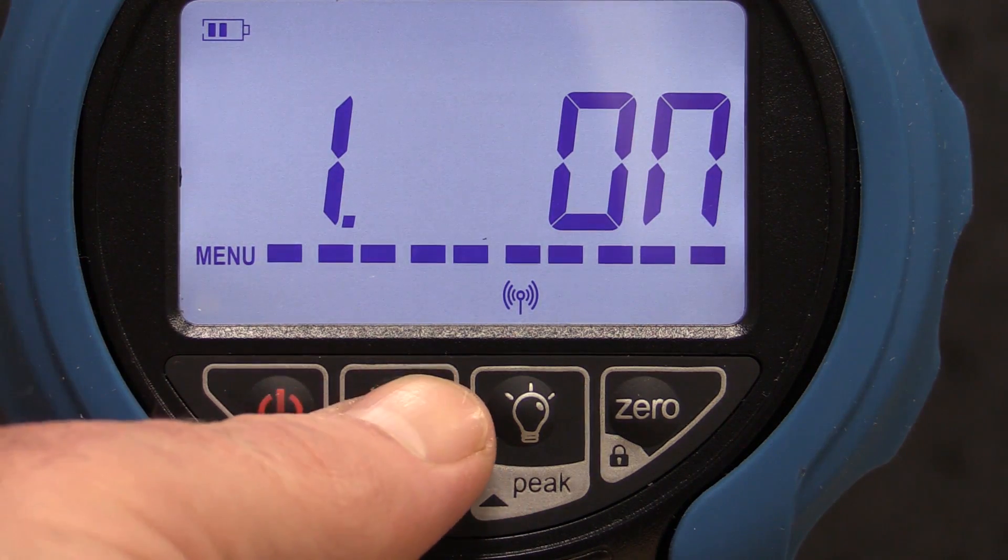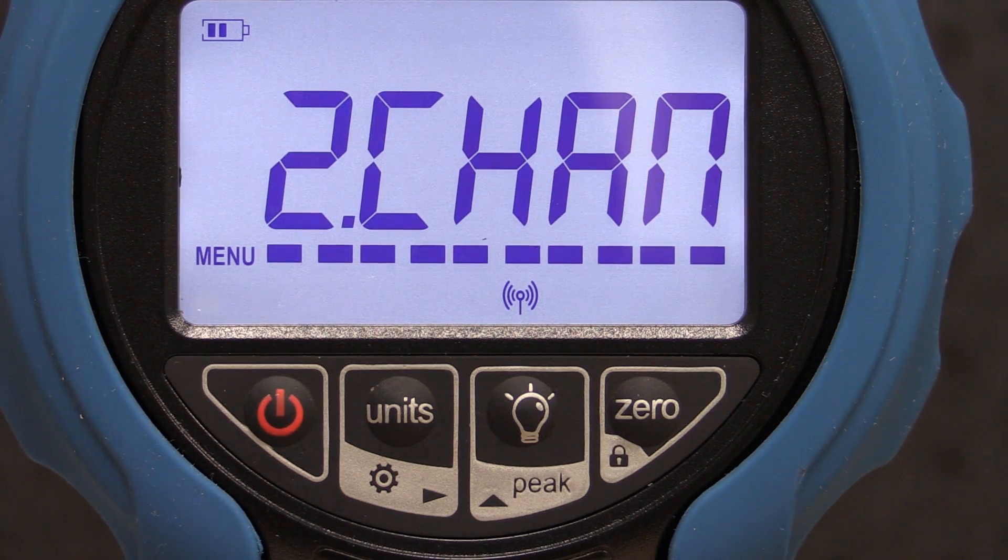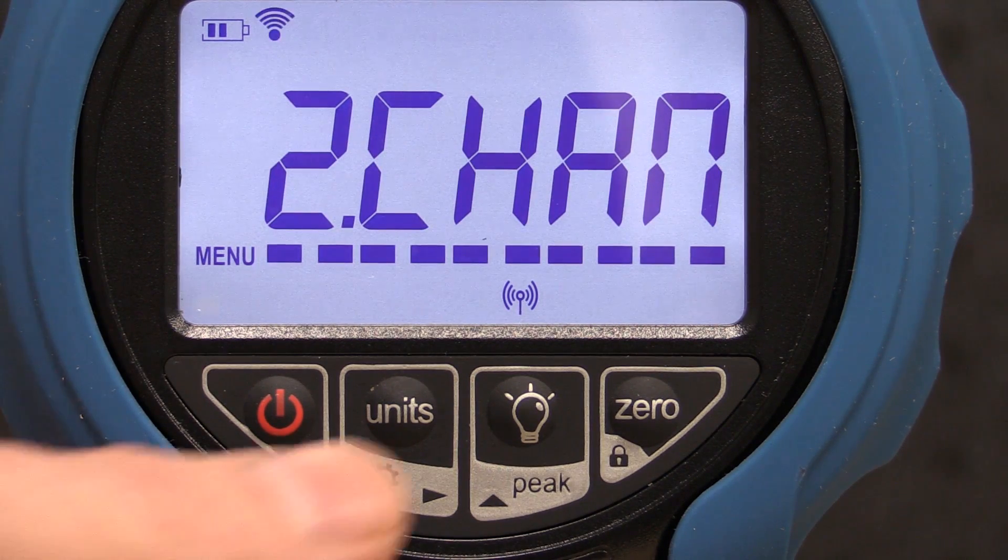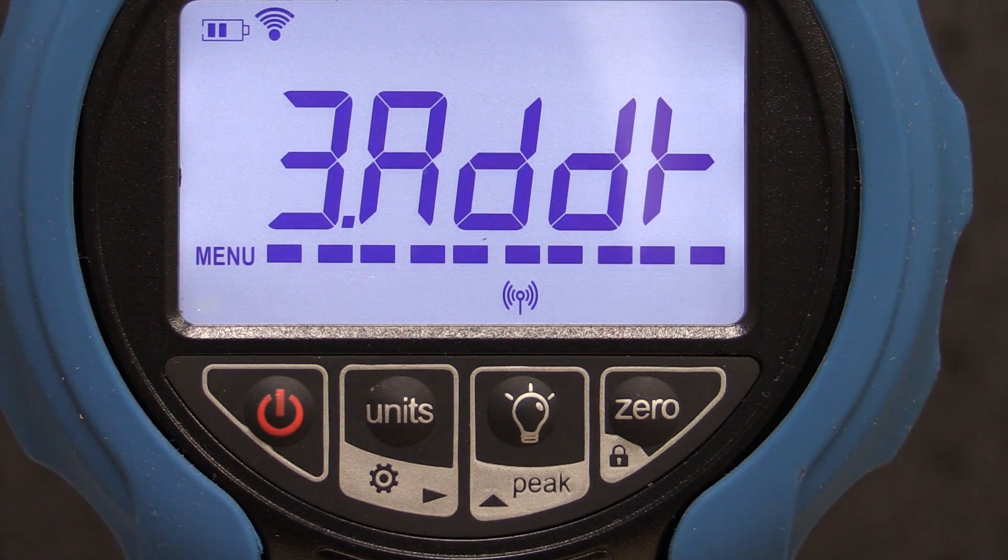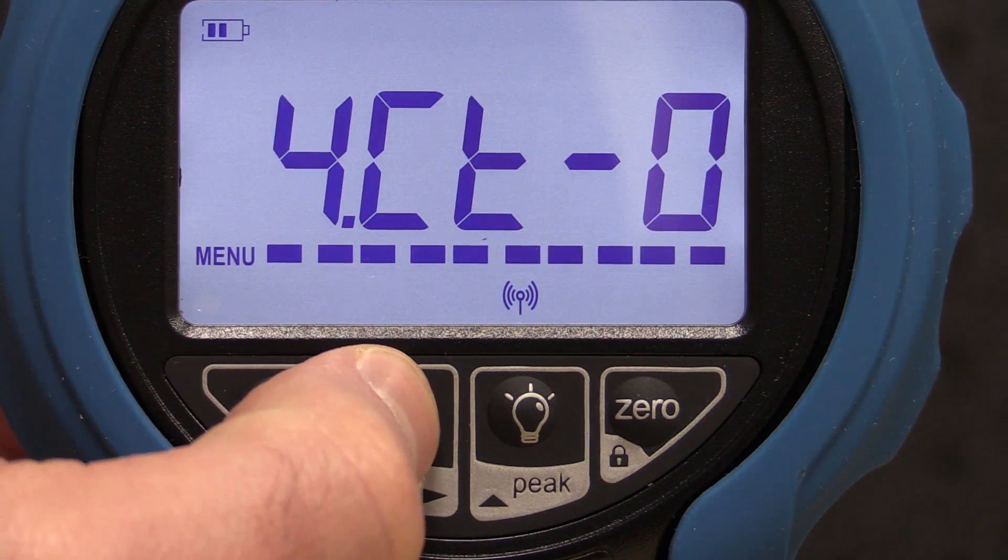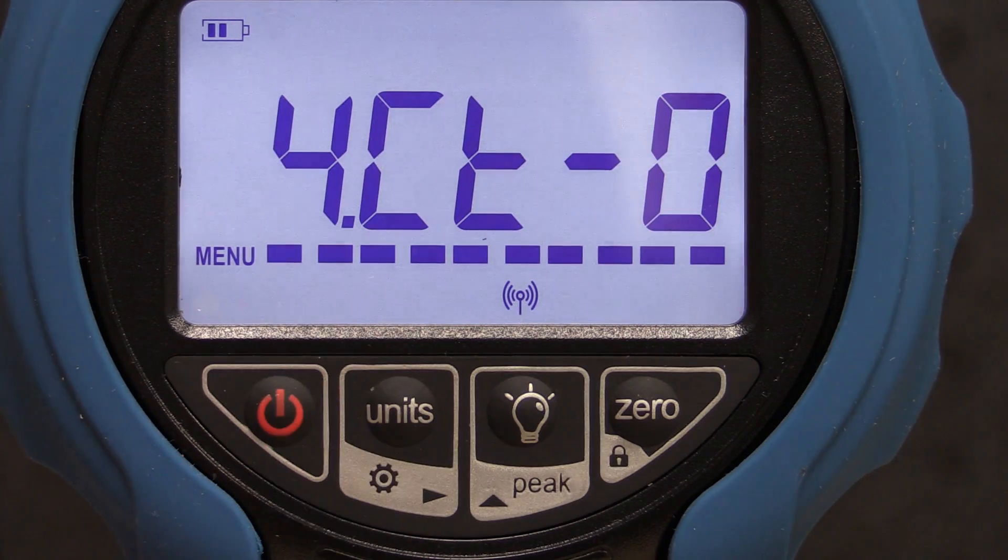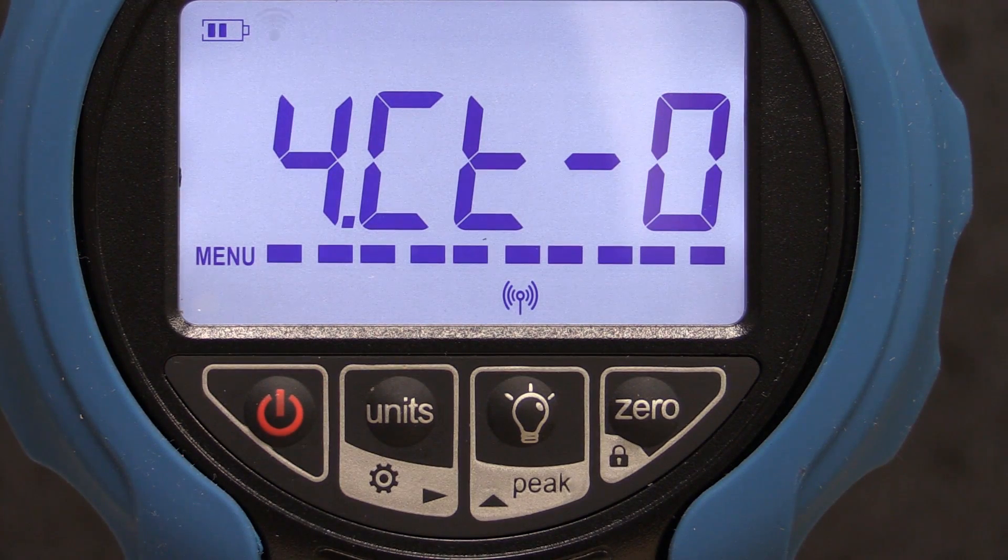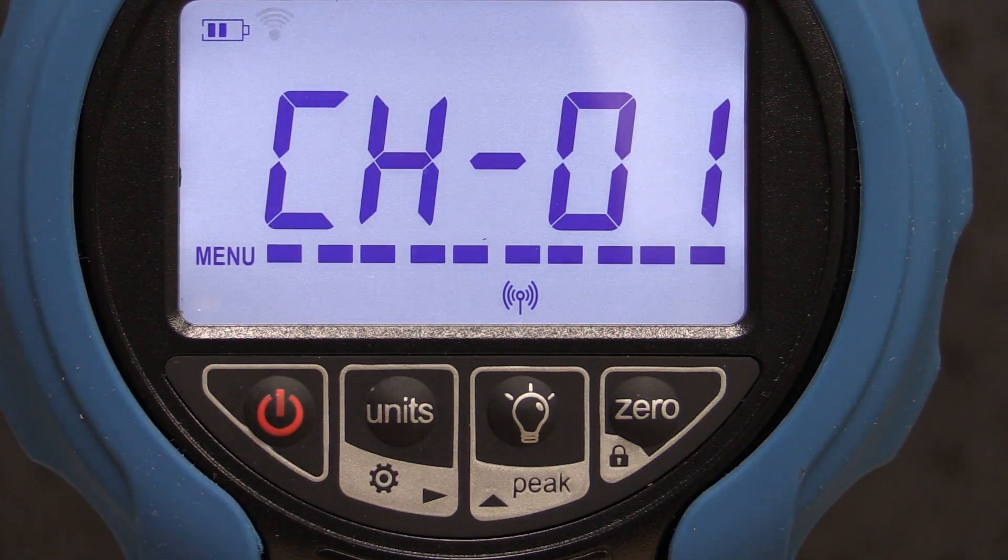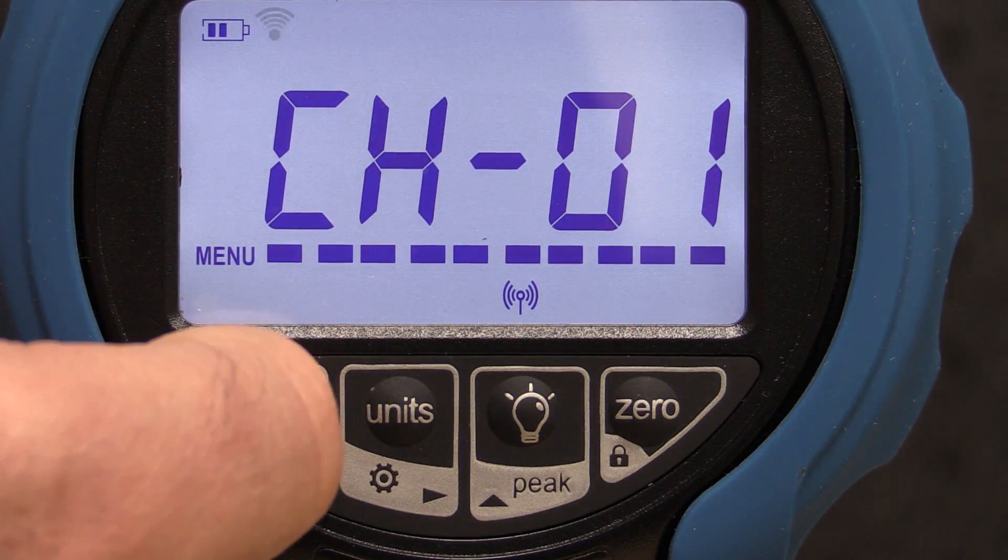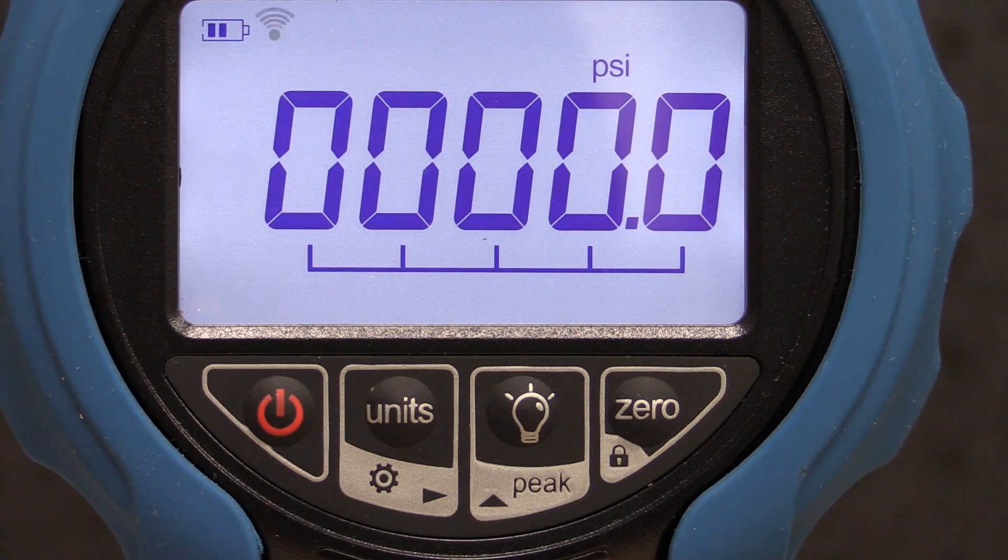The second menu is a channel setting. 15 channels are available. The third menu allows for the device address to be set. The last menu sets the wireless default setting. Zero disables the wireless on power up, whereas one enables it on power up. I will leave the factory default settings as they are and press the power key to escape back to the main display.